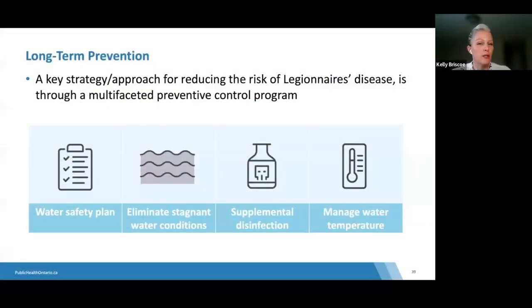So to support long-term prevention, a key strategy or approach for reducing the risk of Legionella or Legionnaires' disease is through a multifaceted preventative program. And the main principles of a water safety plan are aimed to prevent water stagnation, ensure adequate disinfection, maintain appropriate temperatures, and maintain equipment to prevent biofilm, scale and corrosion. All aspects of a water safety plan work collectively to minimize an environment that would support the growth of Legionella, and each aspect on its own cannot guarantee risk elimination, but the key in prevention is to control the risk through a combination of multiple interactive measures.